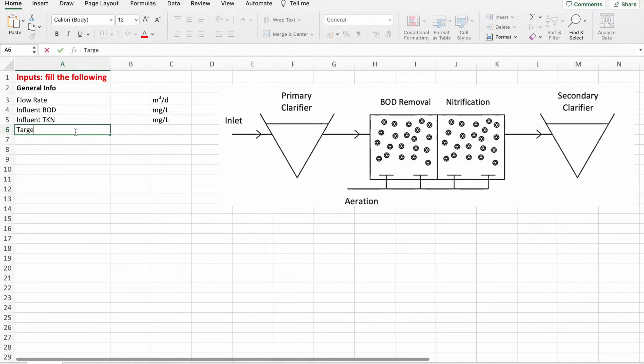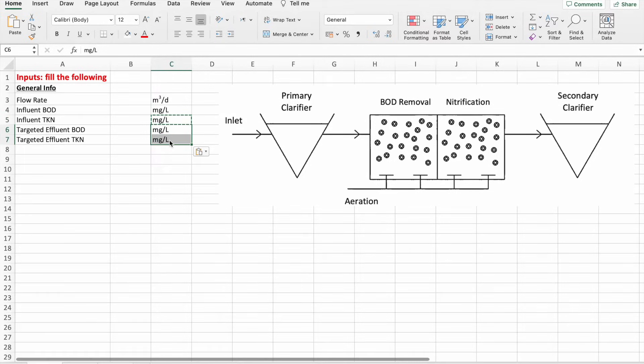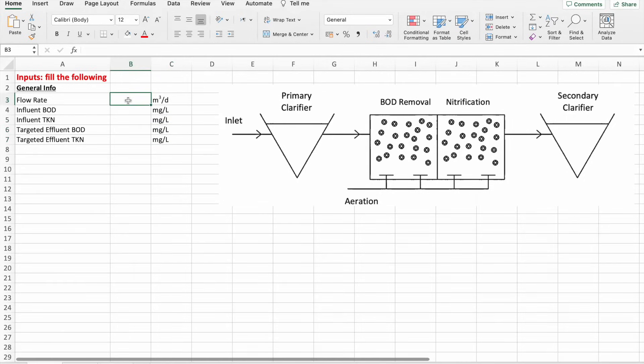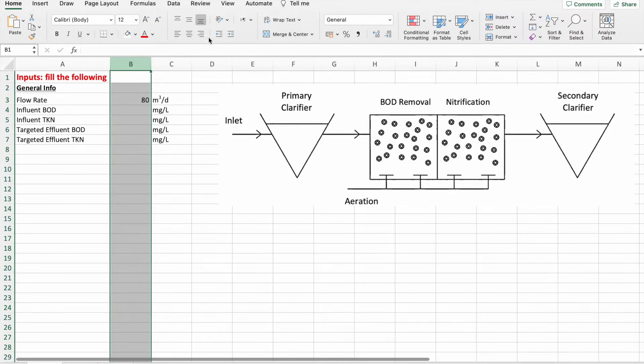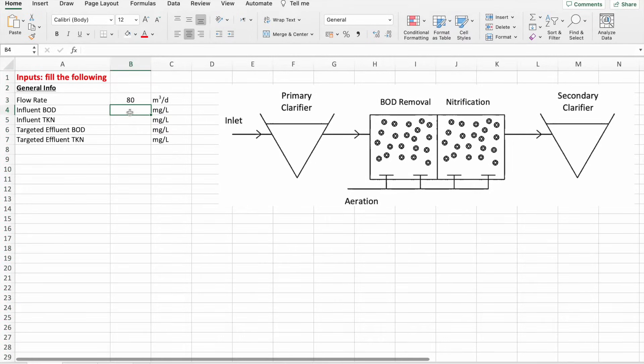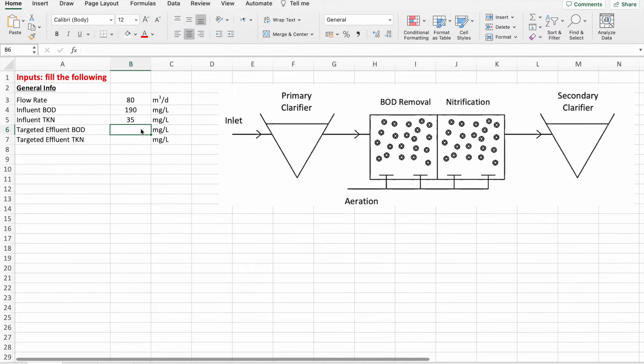I also have to insert the targeted effluent BOD and the targeted effluent TKN, both in milligrams per liter. These are the values we expect to reach at the end of the process when nitrification ends. For our example, we are treating 80 cubic meters per day of wastewater. The influent BOD is 190, the influent TKN is 35, the targeted effluent BOD is 20 milligrams per liter, and the targeted effluent TKN is 5 milligrams per liter.